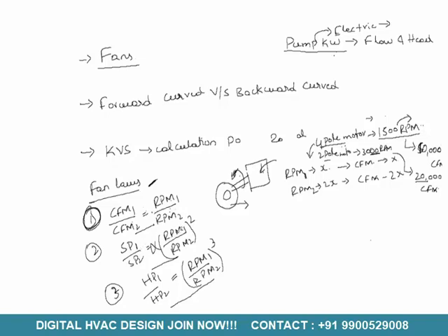Static pressure goes with the square of the RPM: once the RPM increases, the static pressure increases by its square. Coming to the horsepower, when the RPM increases, the HP increases by its cube. So that is an idea.